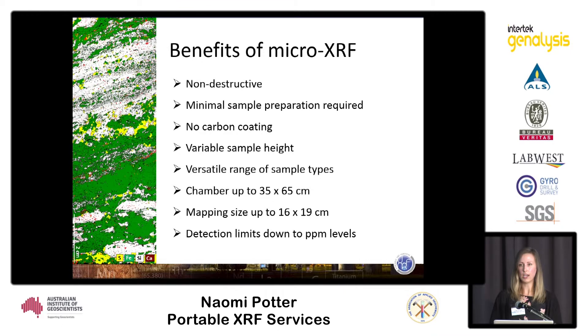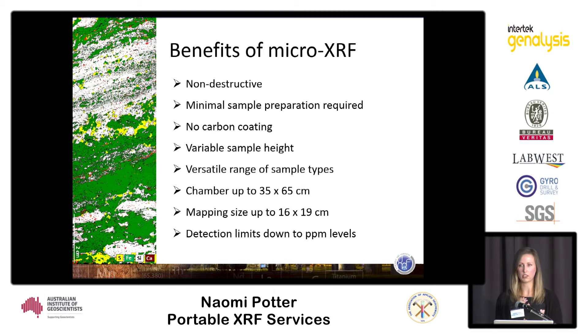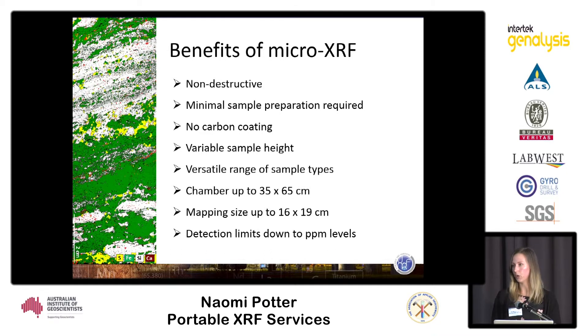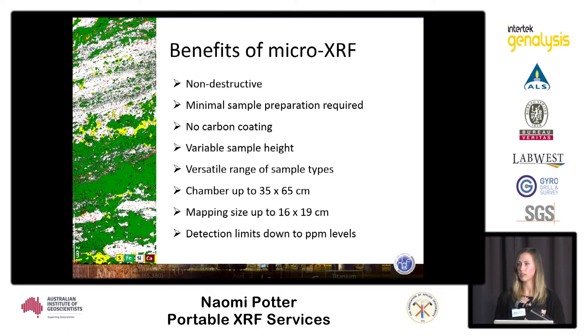It can have variable sample height — when collecting qualitative data you want about a one millimeter variation across your sample height, but for quantitative data you don't need that. Samples can be relatively rough, which means you can measure a versatile range of samples: core, pulps, thin sections, and hand specimens. The chamber for these micro XRF instruments can be up to 65 by 35 centimeters, and the mappable area is 16 by 19 centimeters.